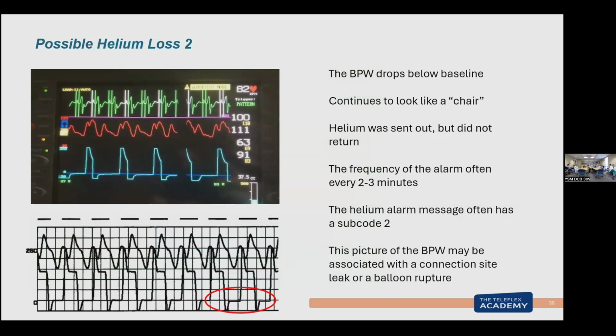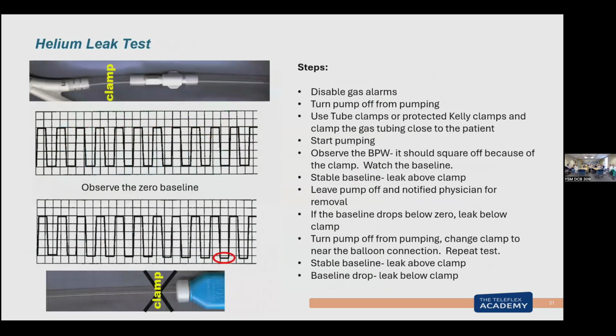This is my helium loss 2, just basically below. That's where I'm more likely going to see a possible helium loss 2, which is a hole in the balloon. You might not see blood. We do an internal leak test on this pump because it can monitor the helium base beat to beat.